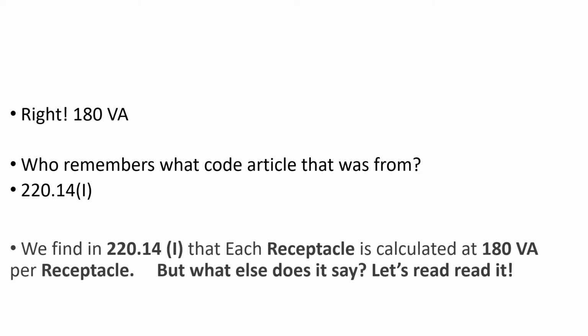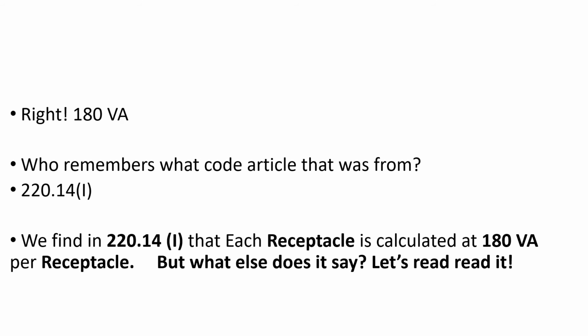220.14(I). We find in 220.14(I) that each receptacle is calculated at 180 VAs per receptacle. But what else does it say? Go ahead and take a minute and read it now. Pause the video if you need to.